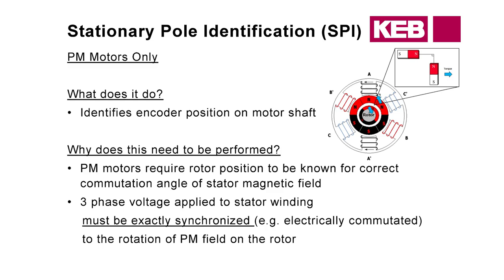The SPI is only done for permanent magnets. This comes down to how the permanent magnet motor works and how the rotor is magnetized. The drive needs to know where the rotor is in relation to the motor poles — the pole pairs. That's why we do the encoder learn, so it can electrically commutate the correct stator magnetic field angle to maintain 90 degrees between the rotor and stator for maximum torque output.